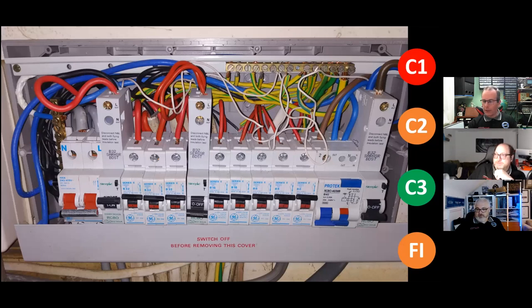And there was a whole pile of other problems in this building. It looked like it had been done fairly well to start with, and then over the years someone's added a bit and someone else added something else, and this is the end result. So all alterations and additions, without taking into account the overall impact on the installation. Yeah, looks like we've got a firm C2 here. I'm with that. Definitely C2s, definitely agree with some C3s in there, definitely agree with some FI as well. So it's good. Right, moving on.